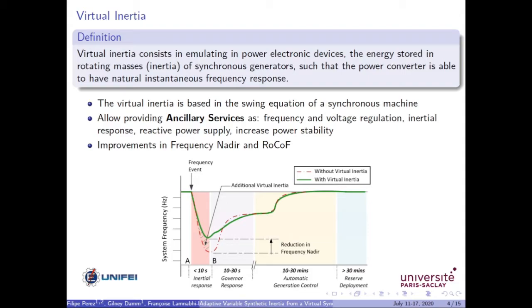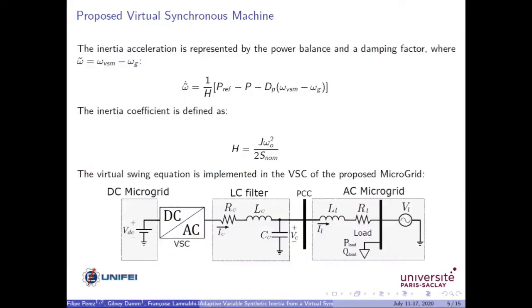Here we can see in this figure the improvement of the inertial response when we are using virtual inertia in power electronic based converters. In green, we clearly see the reduction of frequency nadir when using virtual inertia. The proposed virtual inertia is based on the swing equation of a traditional synchronous machine, given by the inertia acceleration, which is represented by the power balance of the system and a damping factor. This equation brings us an important parameter, which is the inertia coefficient related to the moment of inertia, also the grid frequency reference, and the nominal capacity power of the converter.